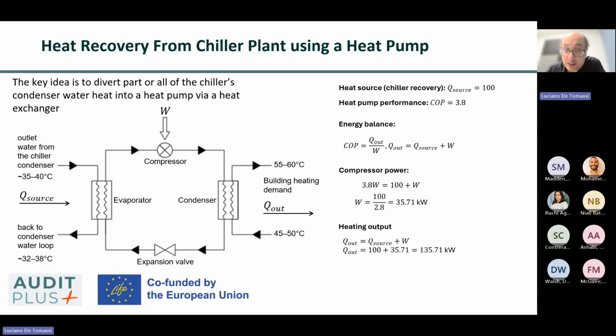A portion of the flow is directed through a heat exchanger or directly through the evaporator of the heat pump, where heat is absorbed from the condenser water. As a result, the water leaving the heat pump evaporator is cooled slightly further within the acceptable range of the loop, helping maintain the condenser return temperature typically around 32 to 38.